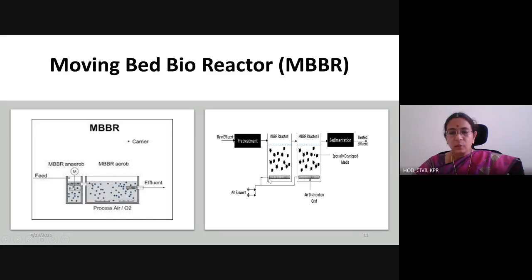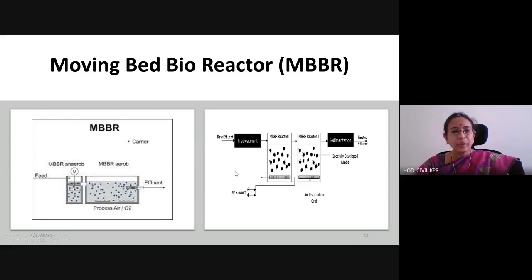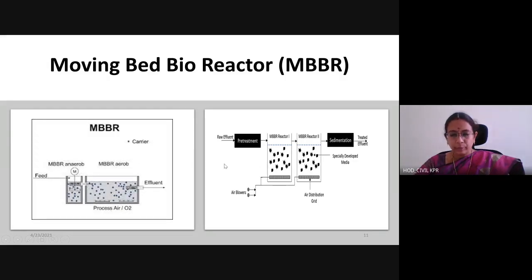Another type is the aerobic-only MBBR. Before entering, the water can be pre-treated using a settling tank, and then taken to MBBR Reactor 1. Air blowers are used to produce oxygen. After MBBR Reactor 1, it can be sent again to MBBR Reactor 2, where all nutrients can be converted. Then it goes to sedimentation and finally the treated effluent can be used. These are the two different types of MBBR reactors: one with combined anaerobic and aerobic, and one with only aerobic.